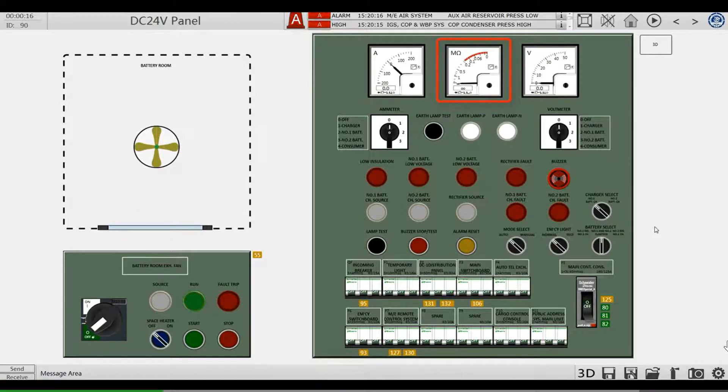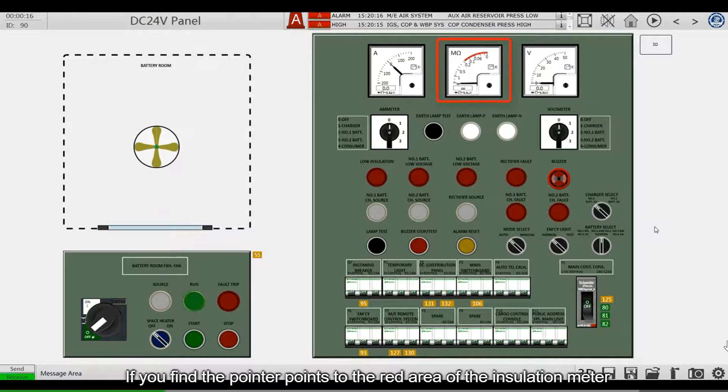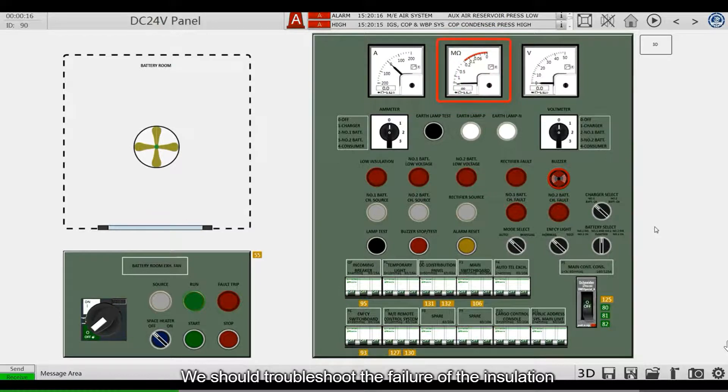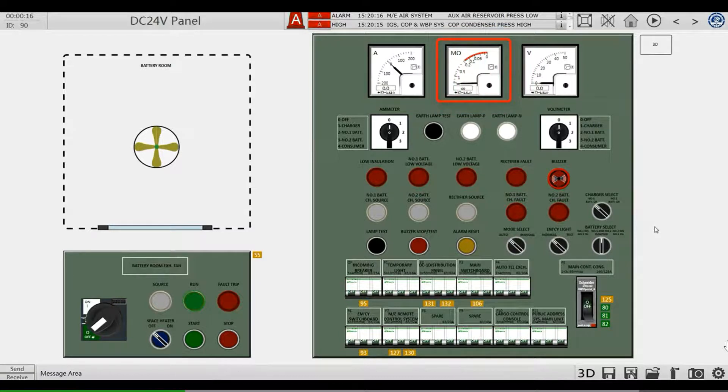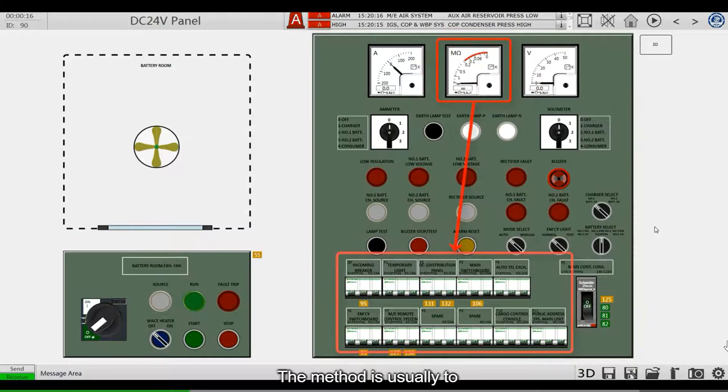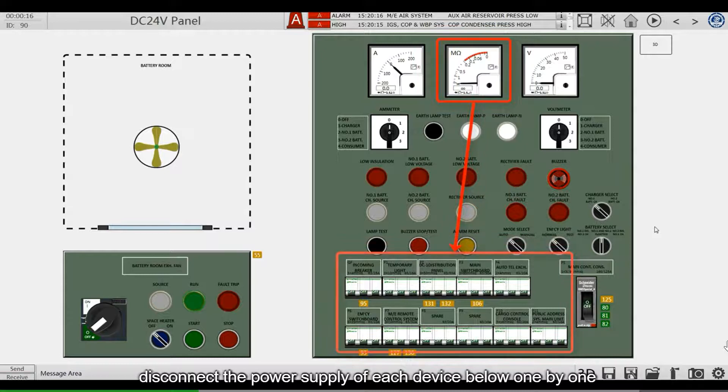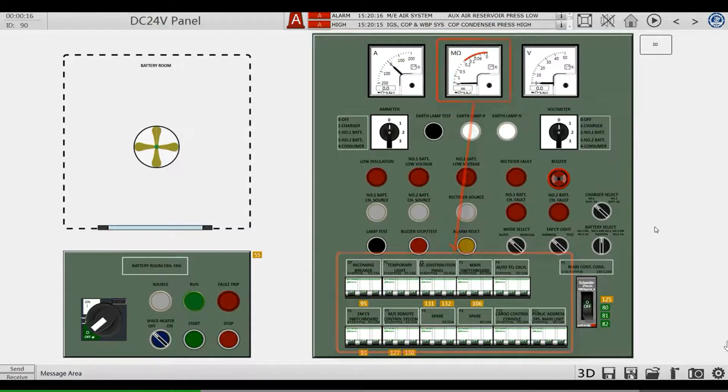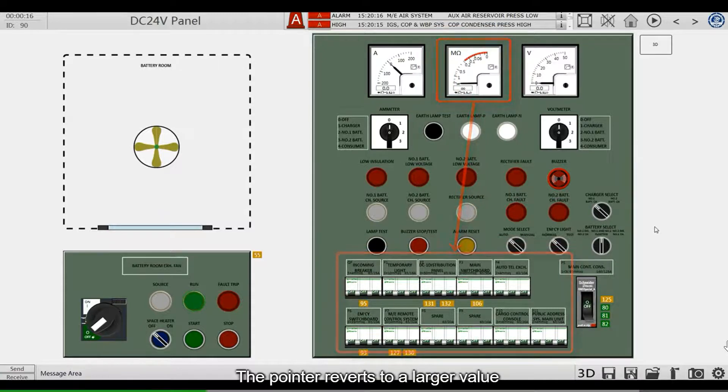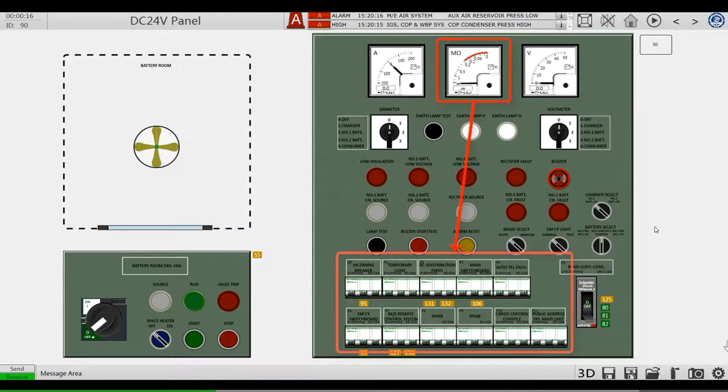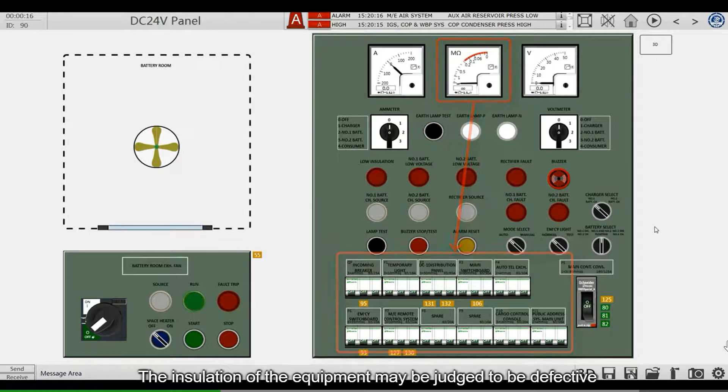If you find the pointer points to the red area of the insulation meter, we should troubleshoot the failure of the insulation. The method is usually to disconnect the power supply of each device below one by one. The pointer reverts to a large value when disconnecting the corresponding device. The insulation of the equipment may be judged to be defective.